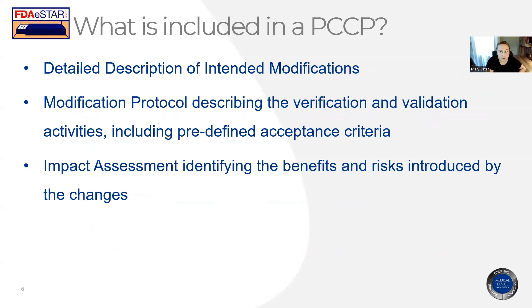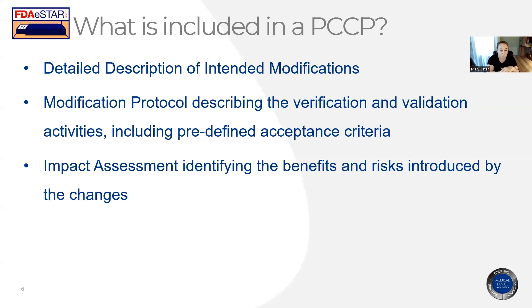What are the basic elements of what needs to be included in a PCCP? The first is a detailed description of the intended modifications — listing all the specific changes, what those changes are, and why those changes are appropriate. You will also identify whether it's a locked or adaptive algorithm. The next element is the modification protocol, which describes the verification and validation activities including predefined acceptance criteria for these changes. This is perhaps the most important part, because the FDA needs to buy in and ensure that your testing will support those changes and claims — they are pre-evaluating your testing so that as long as you meet everything outlined in the PCCP, the FDA is confident it will support your modifications.